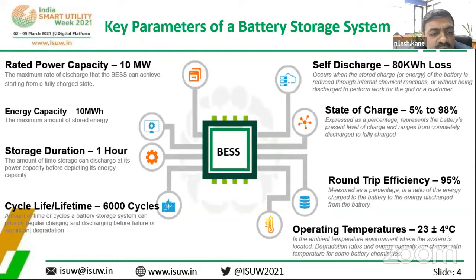And these are the limits: rated capacity is 10 megawatt hour, 10 megawatt for 1 hour, and 6,000 cycles is the lifetime of the battery. We are operating at 23 plus or minus 4 degrees centigrade. We have kept 200 tonnage of air conditioning for maintaining this, with round trip efficiency of 95%. State of charge is from 5% to 98%, obviously almost 0 to 100% for this lithium ion battery storage. And the self-discharge loss is 80 kilowatt hours. Next.